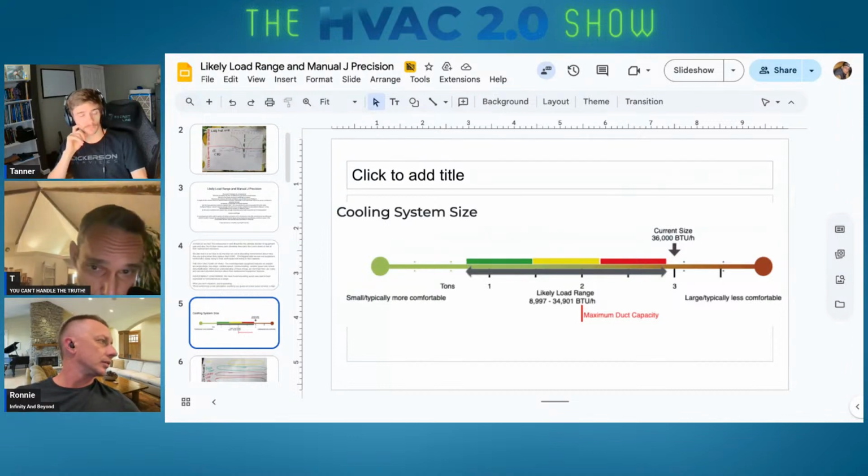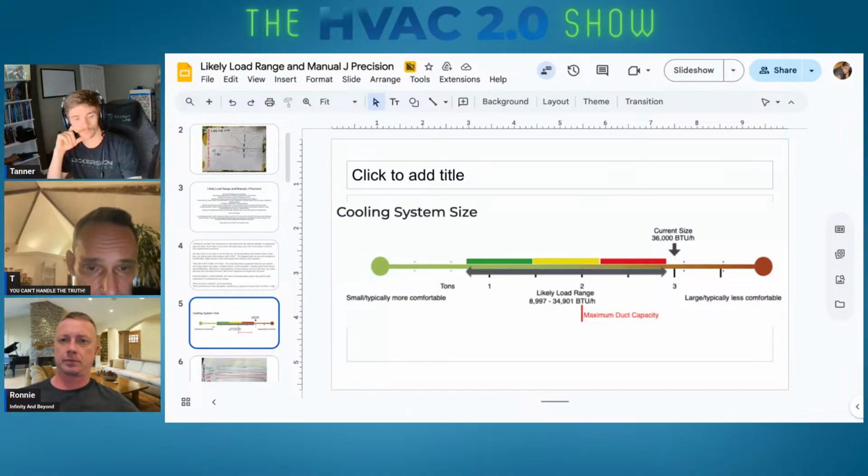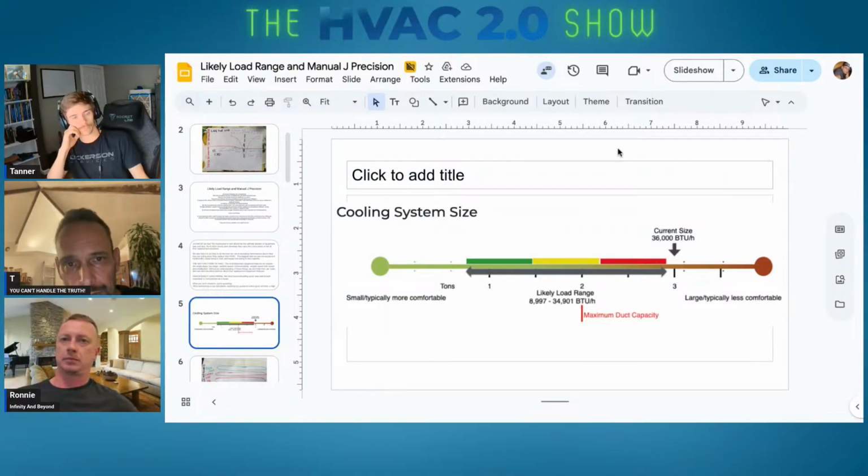And you could do Measure Quick and true flow, and give them both those reports, which will explain to them exactly how much capacity they were getting. So they'll be like, "Oh, so I had a 3-ton system all along, but I was only getting 2-ton of delivered capacity, and I was comfortable. I guess it's a 2-ton house then."